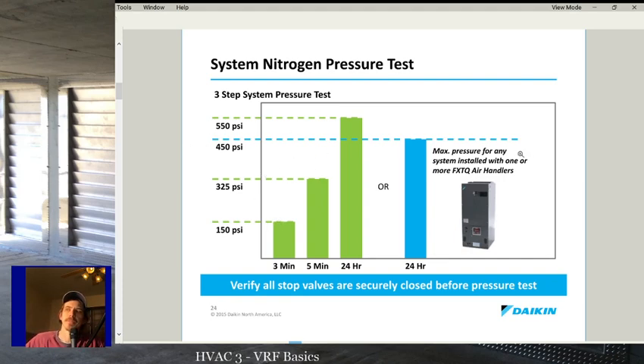So then take it up to the maximum pressure allowed for test pressure and let that sit for as long as possible. If as long as possible is 15 minutes and you've got a good sensitive gauge, then fine, it's 15 minutes. If the longest you can let it sit is 2 weeks, let it sit 2 weeks. The longer you can test, the less sensitive of a gauge you need to find your leak.